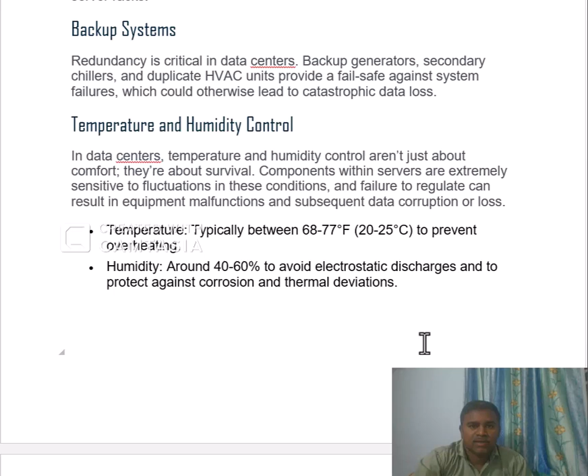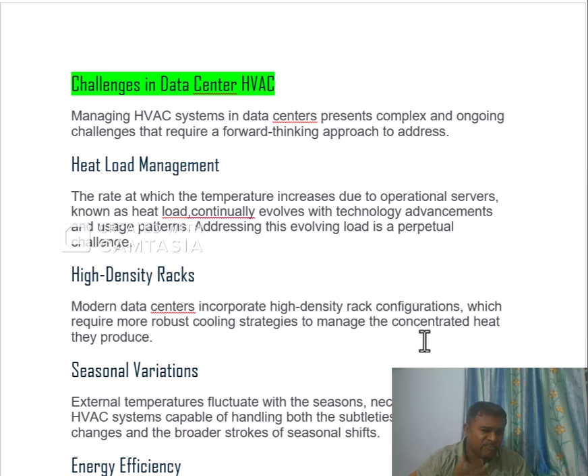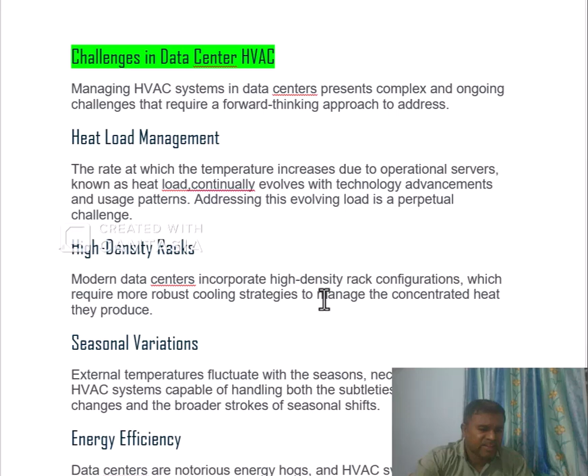Coming to this, when designing data centers, it is very important to take the heat load estimation related to the operating servers, as well as the amount of heat dissipated by the server, the kilowatts it is generating, and how much heat is generated per kilowatt. It's very important to get this from the vendor before designing. And coming to rack density, as the density of racks increases, the servers also increase, and the concentration of heat also increases. Seasonal variation also you need to consider, as well as fluctuations.